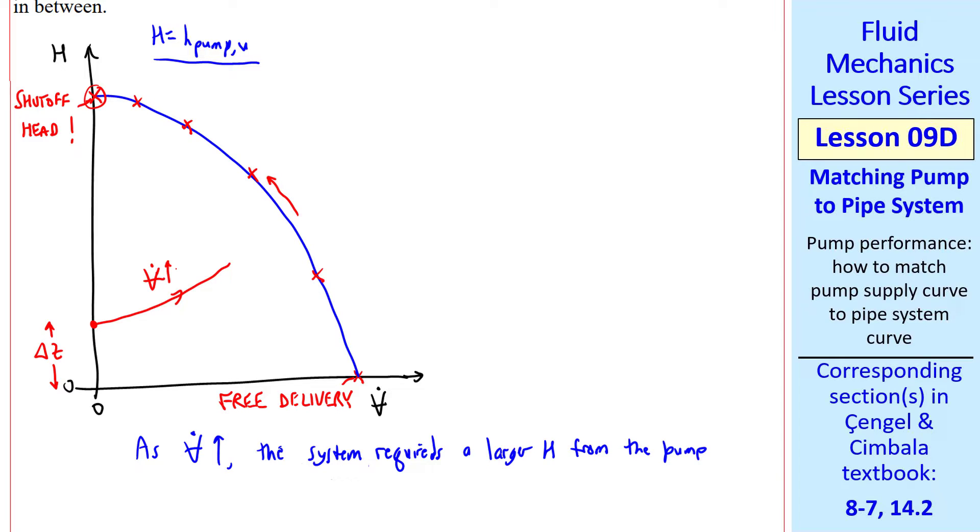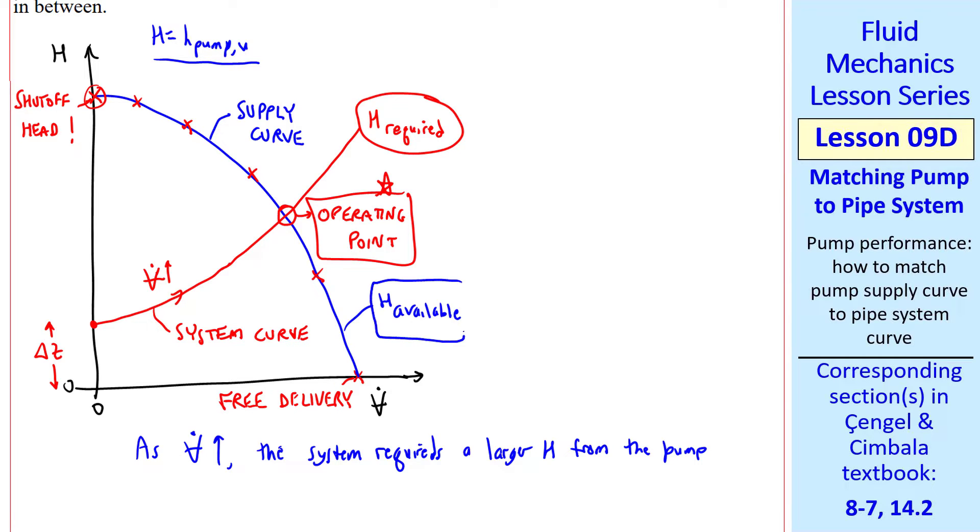The curve typically slopes up like this as V dot increases. At this point, we'd need a pump that can supply this much head at this flow rate. Again, we have a heftier pump than that, but as we keep going up in volume flow rate, eventually this curve crosses our pump performance curve. Our pump would not be able to deliver anything beyond this point where these curves cross. In fact, this point is the operating point. We typically label these curves the supply curve. This is the head supplied by the pump and the system curve, which is what the pipe system requires.